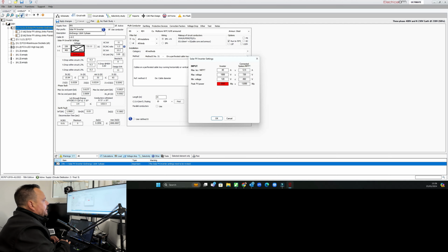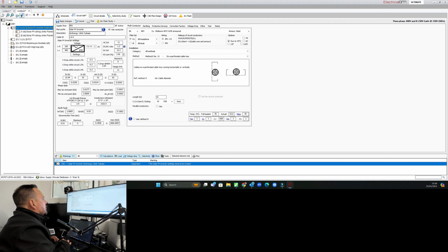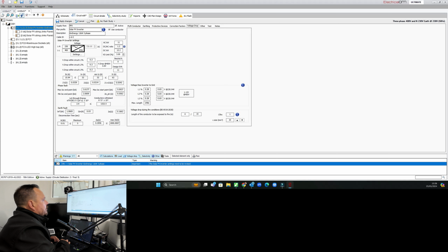So we've got our peak power, peak PV power. We'll set that to 13,200 just to match what's actually going on with our inverter. So we've cleared that particular fault away now, and we've got the volt drop within L1, L2 and L3 shown as 0.2. If we have a look in the actual list here, you can see what we've got in terms of our volt drop as well.